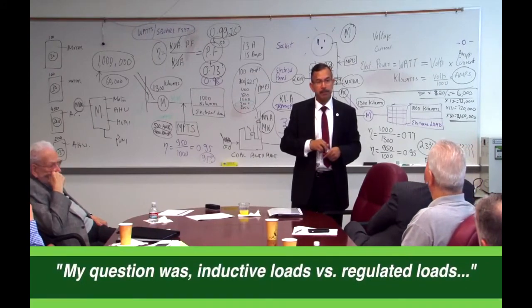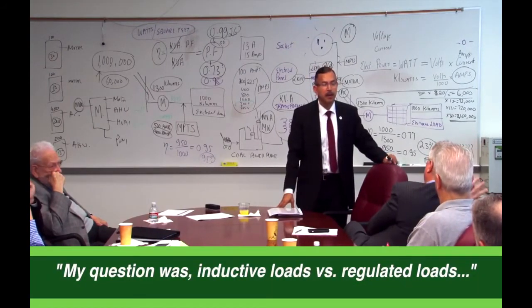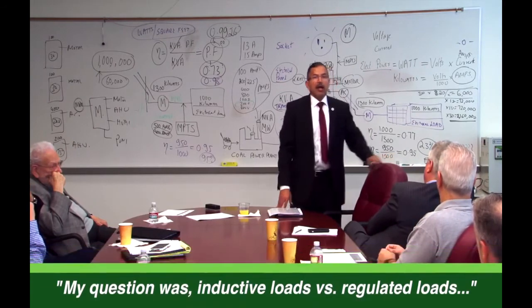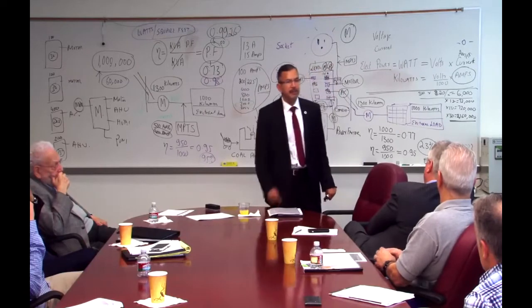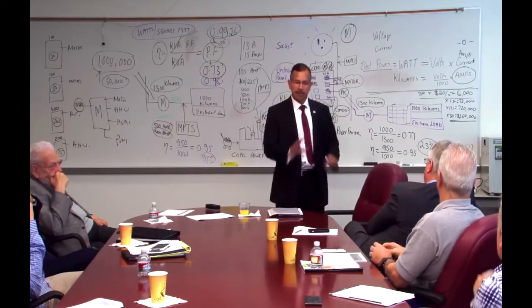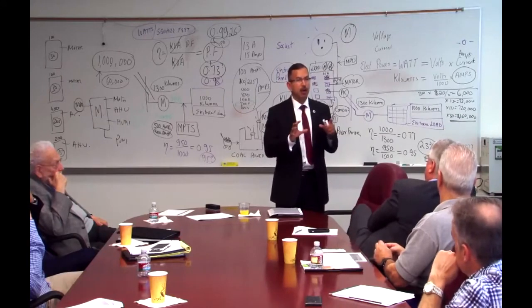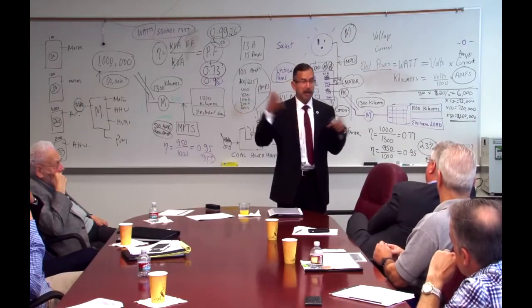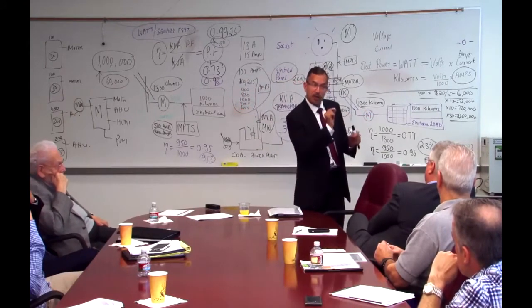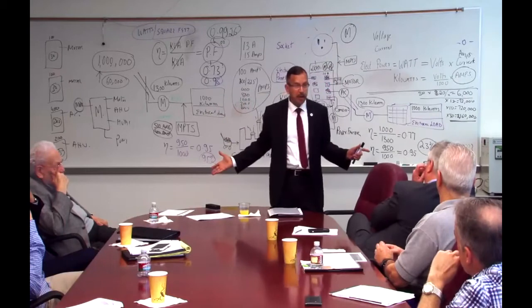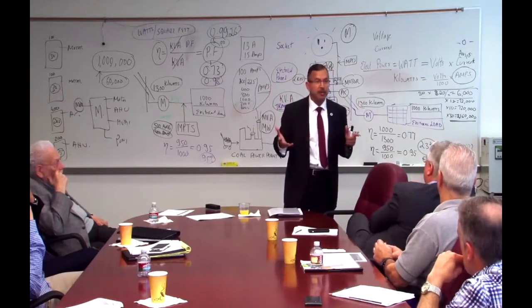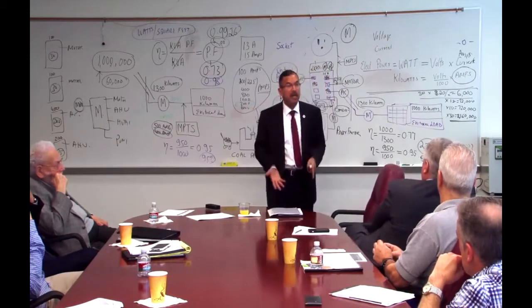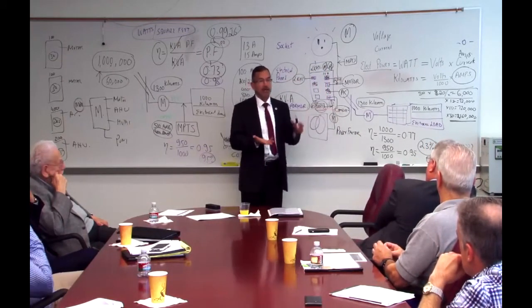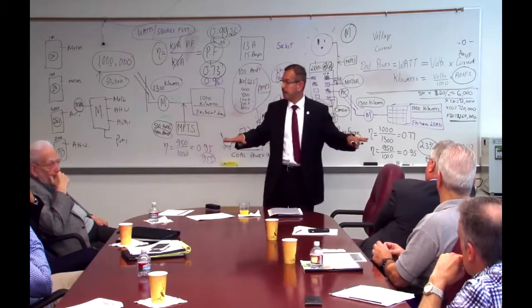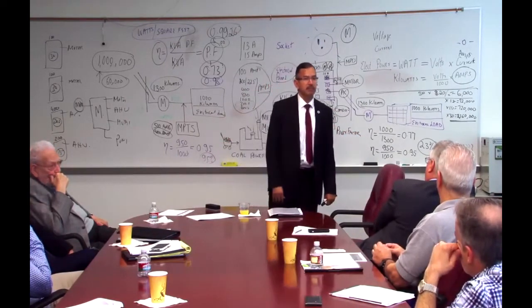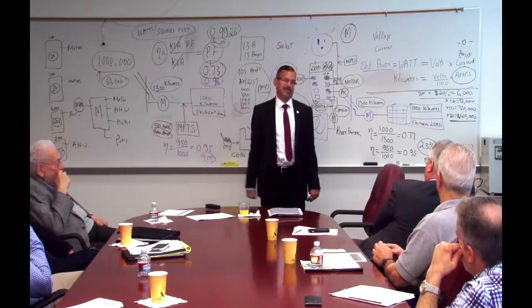My question was inductive load versus regulated load. All electronics is inductive load, they're all active components to start with. They're all inductive loads and they have fans in them. They may be small, but little drops of water make the mighty ocean. Every computer is a little drop of water, and when you have 1,000 computers in your building, you've got harmonics to the level of 50 to 80%. That increases the current by 10 to 15%. When you have an MPTS unit, you can mitigate the increase in harmonic currents inside your wire while protecting your equipment.